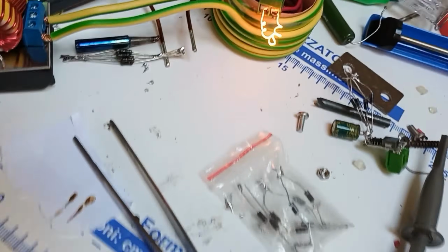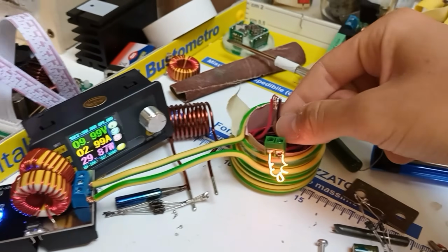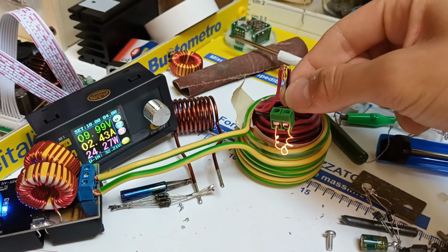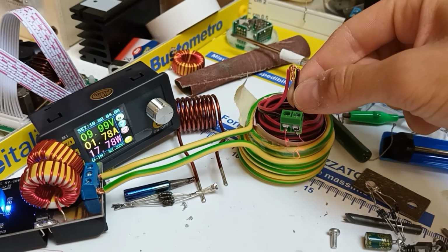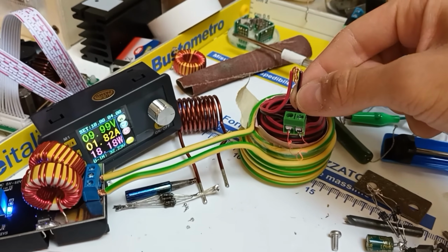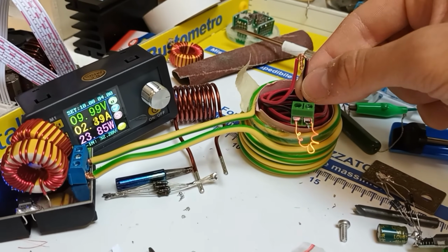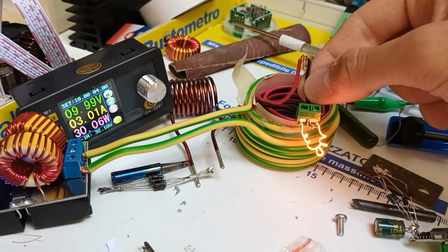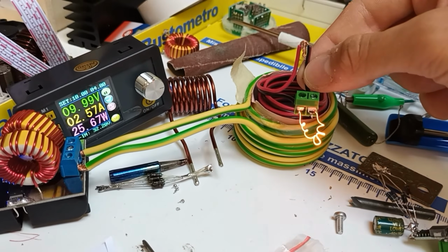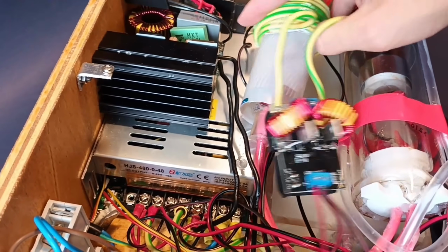It consists of 2 coils of wire that are magnetically coupled, so it is possible to transmit power from the green-yellow cable situated on the outside of the high voltage circuit to the red cable, which powers the glowing filament that now is simulating the inside of the tube. And what you're seeing now is the final prototype that I'm using inside the machine.